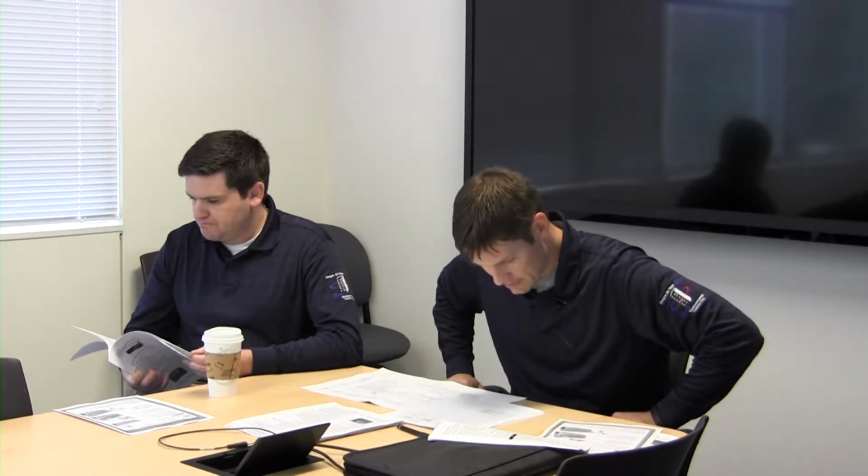Going back one more page is your refrigerant cycle. So there's your Carnot cycle for your class. It does give you, if you assume a 95-degree outdoor temperature, 80 degrees indoor, those are the refrigerant pressures and temperatures that you should see in a proper operating system.